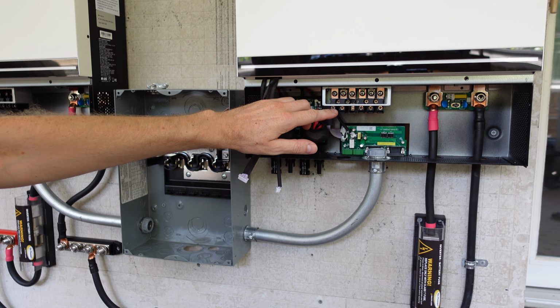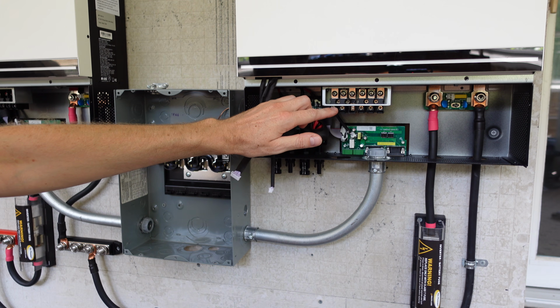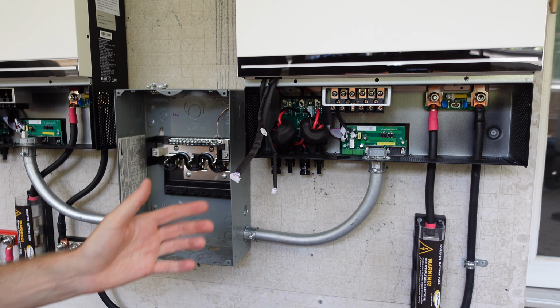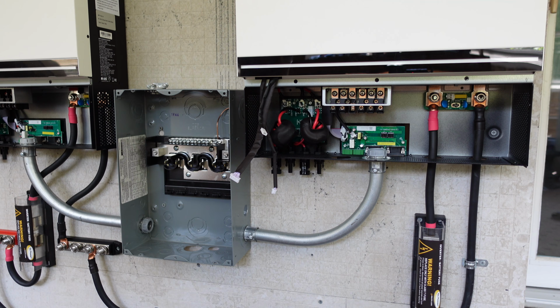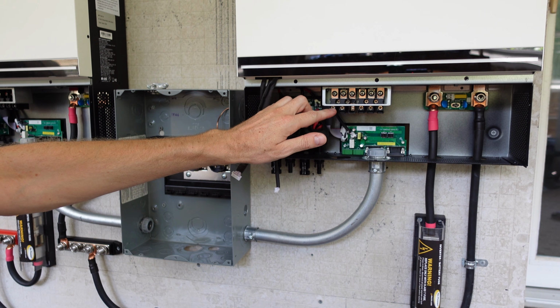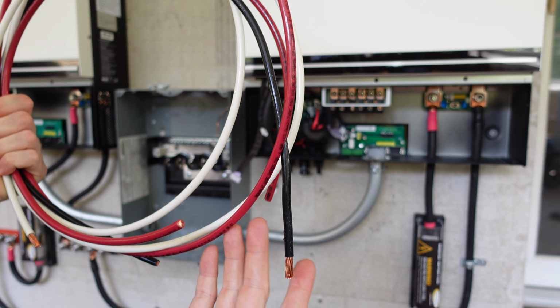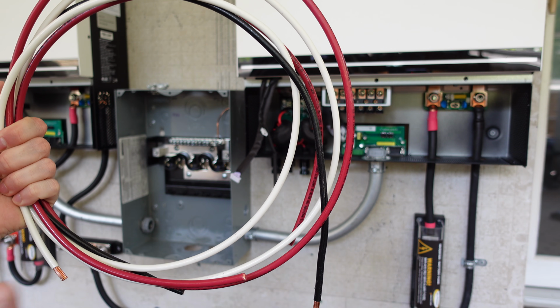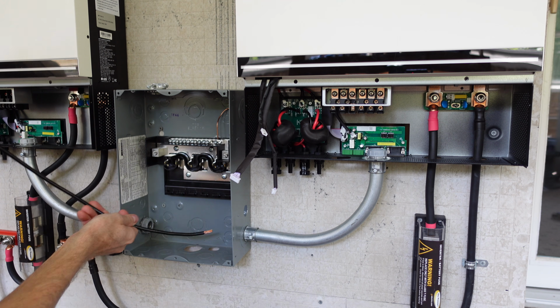Additionally, I don't think there's any way you're going to get 4 gauge wiring on these terminals. I've not personally tried it, however, this number 6 seems to take up almost the entire area of this terminal. So I have black for leg 1, red for leg 2, and then white is for the neutral, of course.